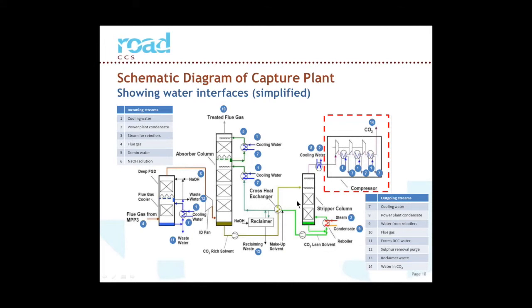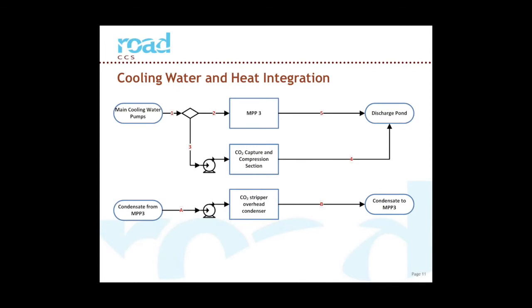This slide shows a recap of our chosen cooling system and mentions the condensate that's used to cool the overhead stripper condenser. So the cooling water supply for the power station we take after the main inlets for the power plant, and that's because the main cooling water intake had enough margin for us, and it's quite expensive and a difficult permitting challenge to get a new cooling water intake. So we use the existing intake, but we take the cooling water round MPP3 to the discharge pond. It would be cheaper to put it back in before MPP3. That would give us much shorter ducts because of the plant layout. But then we'd be putting warmer cooling water into MPP3 into the power plant and reduce its efficiency. So that's the basic layout for the cooling water.